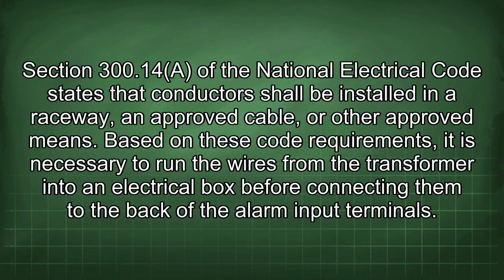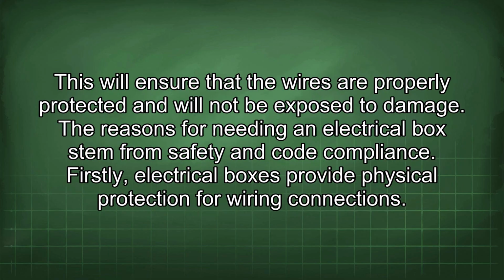Section 300.14 of the National Electrical Code states that conductors shall be installed in a raceway, an approved cable, or other approved means. Based on these code requirements, it is necessary to run the wires from the transformer into an electrical box before connecting them to the back of the alarm input terminals. This will ensure that the wires are properly protected and will not be exposed to damage.